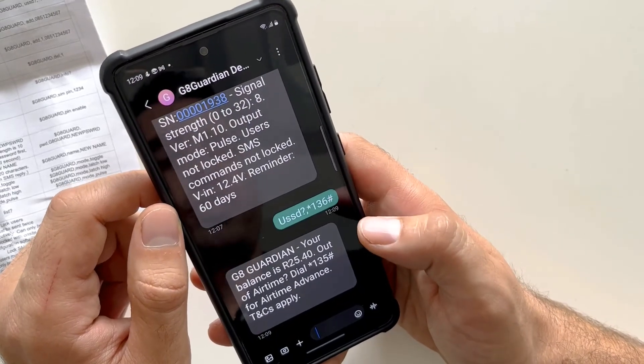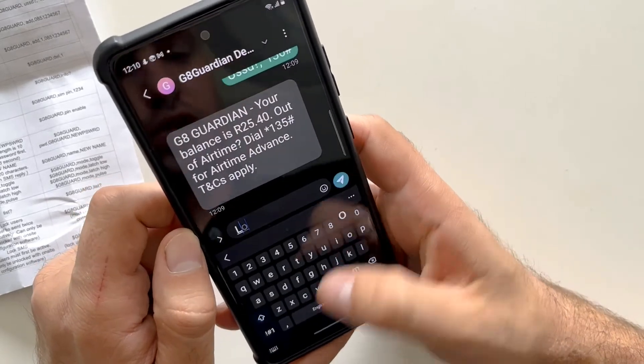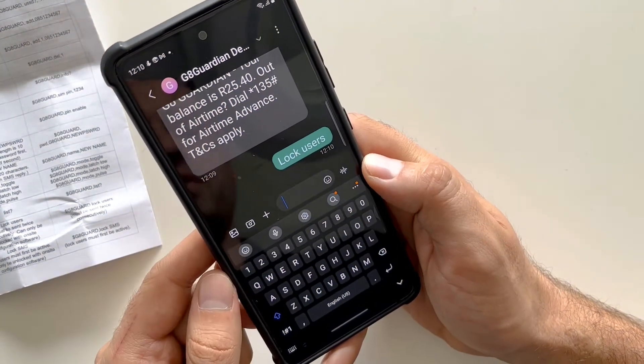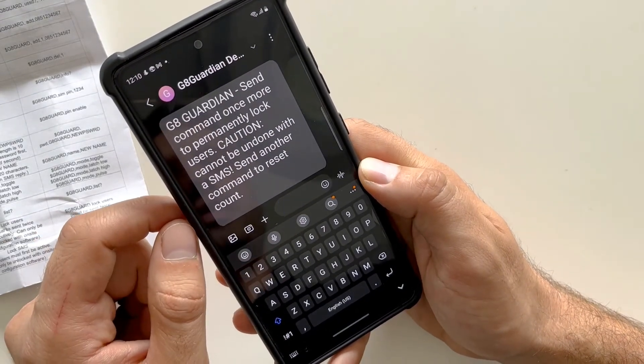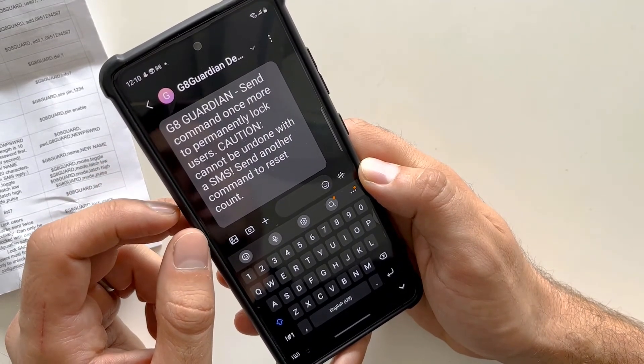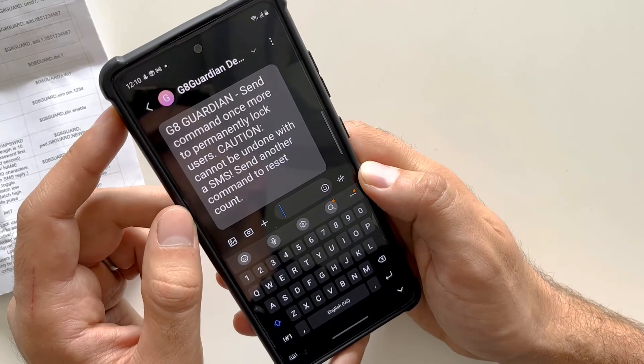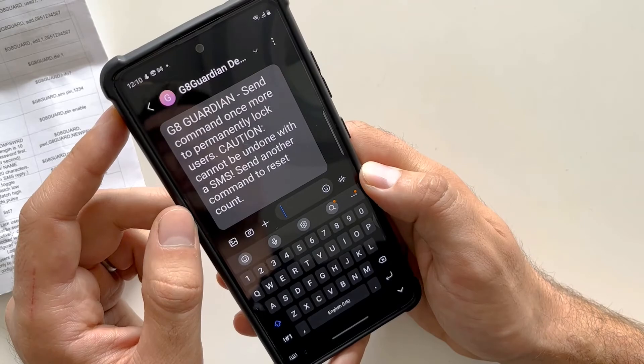Your G8 Guardian is now programmed correctly. If you wish to lock users, type: LOCK USERS and send that. The G8 Guardian will give you a reply telling you that if you send the command once more you will permanently lock the users. This cannot be undone by SMS — you can only undo it using the desktop application. So make sure that when you leave site, if you do want to lock users, all the users have been programmed into your G8 Guardian beforehand.